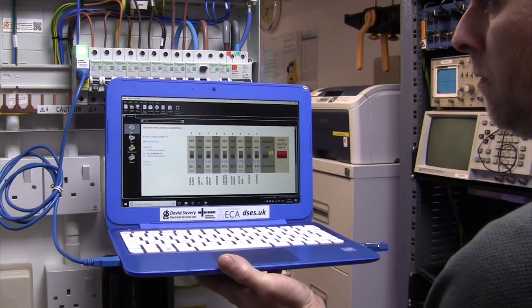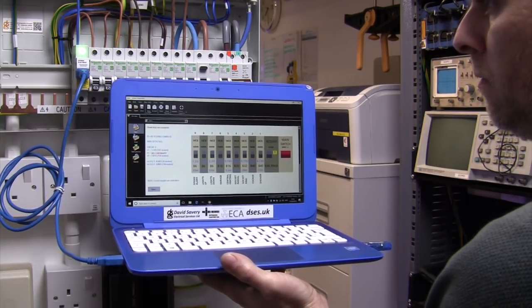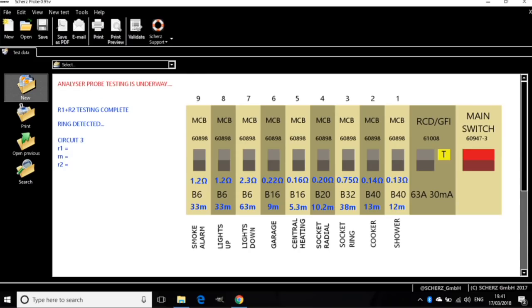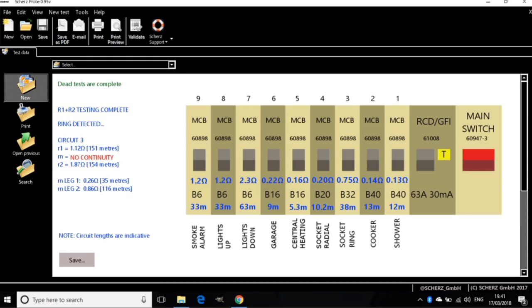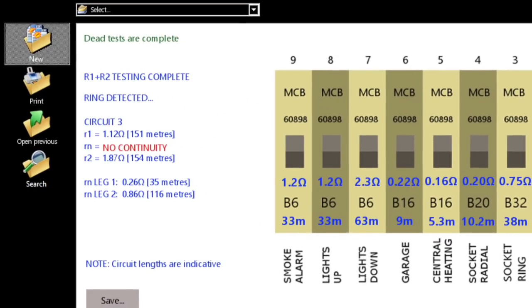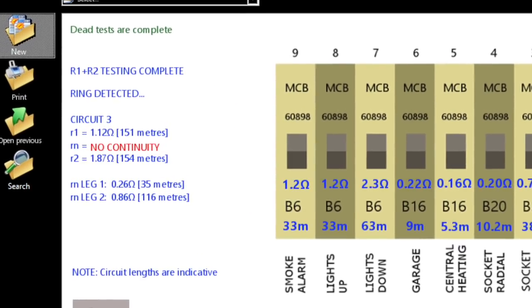Here, I've disconnected the neutral in my ring circuit to simulate a break. If there is a break in the ring, then the ping pulses will be reflected back down each leg from the break point, thus giving you an indication of how far away the break is and where you need to be concentrating your fault finding efforts, which I'm sure I don't need to tell you is an absolute boon.